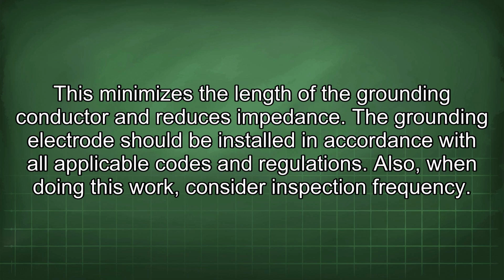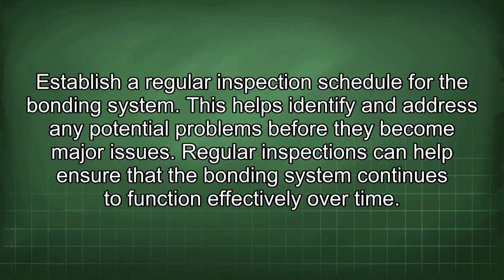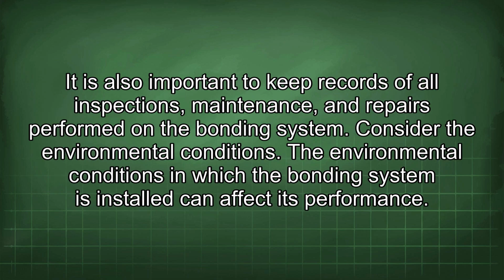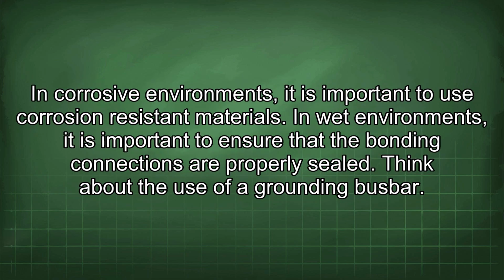Also, when doing this work, consider inspection frequency. Establish a regular inspection schedule for the bonding system. This helps identify and address any potential problems before they become major issues. Regular inspections can help ensure that the bonding system continues to function effectively over time. It is also important to keep records of all inspections, maintenance, and repairs performed on the bonding system. Consider the environmental conditions. The environmental conditions in which the bonding system is installed can affect its performance. In corrosive environments, it is important to use corrosion-resistant materials. In wet environments, it is important to ensure that the bonding connections are properly sealed.